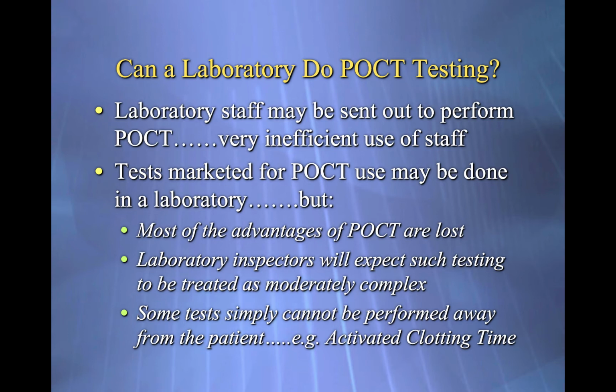The laboratory inspections, when your inspector comes in, they're going to look at those tests and say, well, I expect you to treat those all, even if it's waived, as moderately complex. I'm going to expect you to do proficiency testing, even though for waived tests in a point-of-care setting you don't have to. We'll talk a little bit more about that. But they're going to expect that each test in a laboratory is handled like every other test.